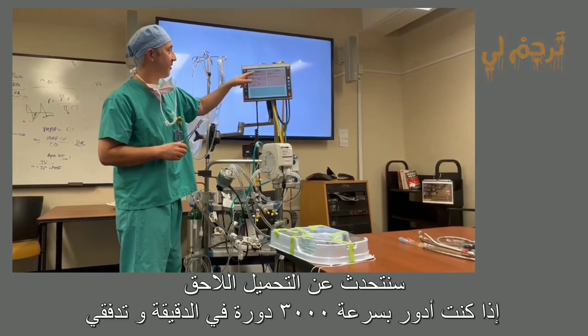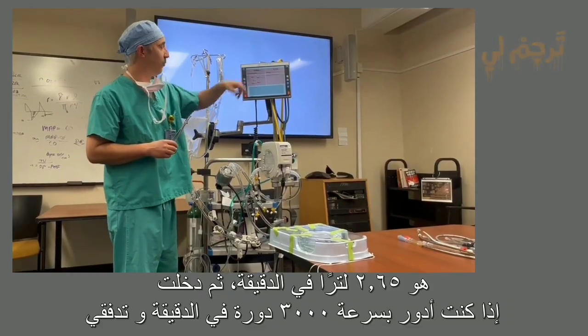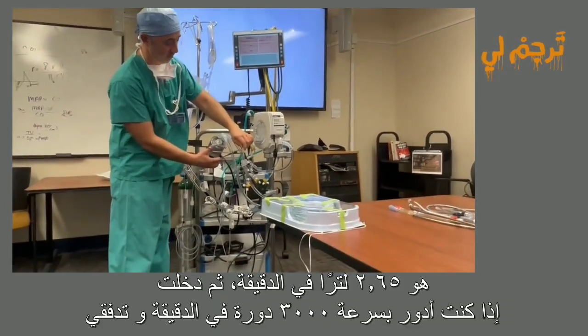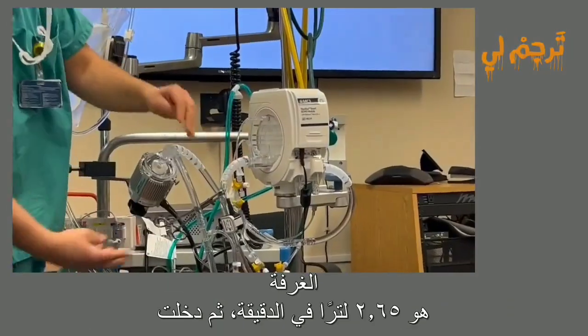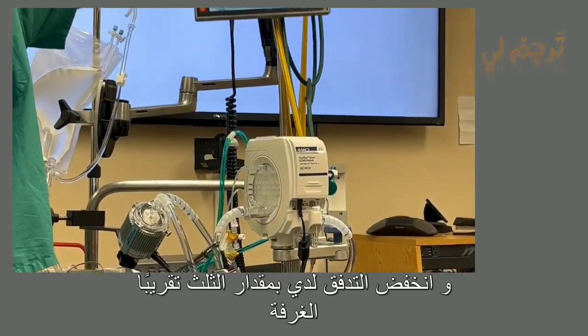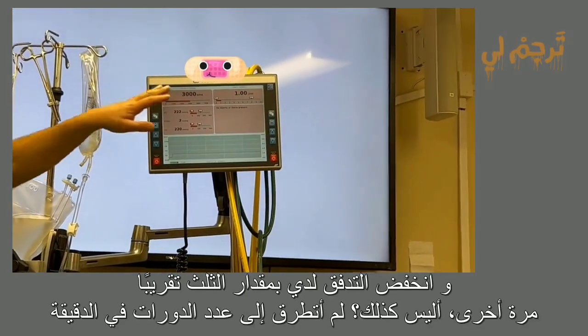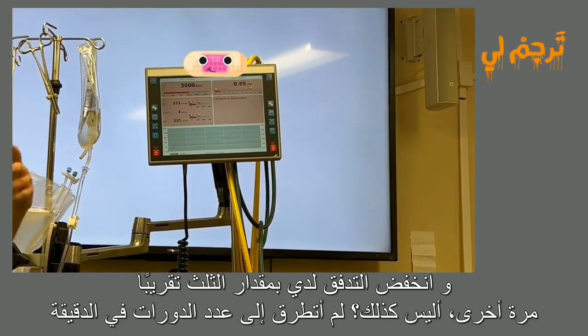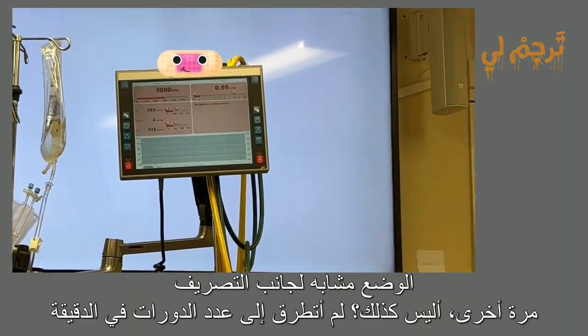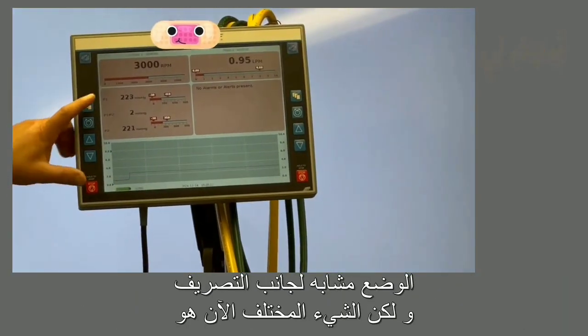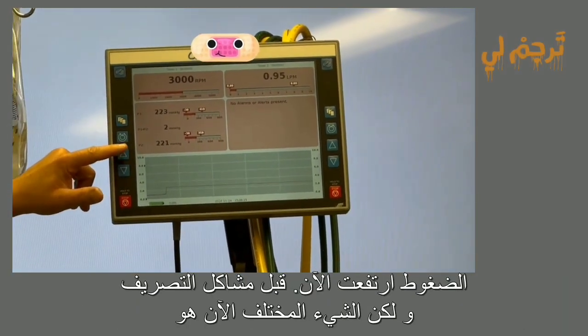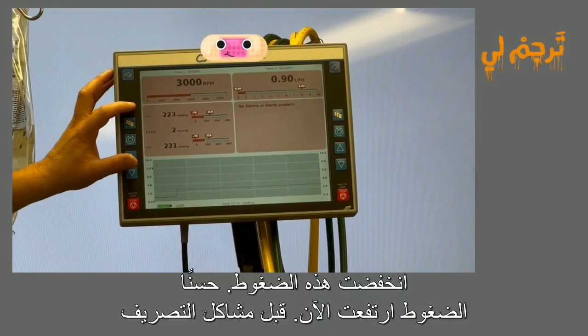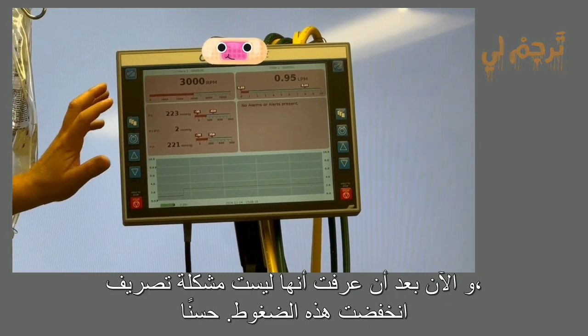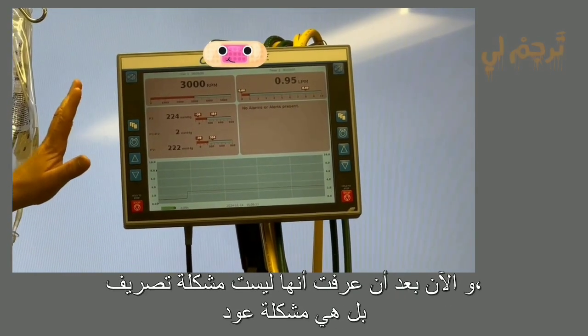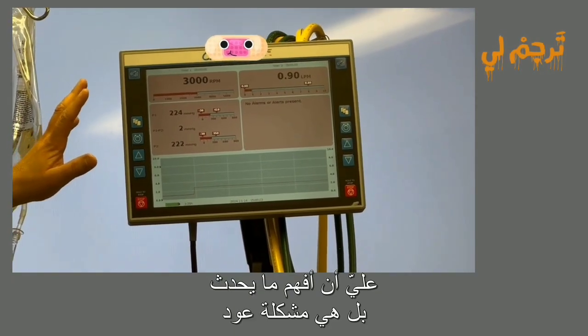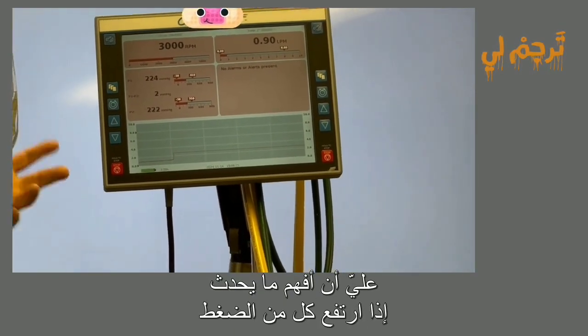If I'm spinning at 3,000 RPM and my flow is 2.65 liters a minute, and then I come into the room, now my flow is down almost a third, right? And I haven't touched the RPMs. Similar situation as the drainage side. The thing that's different is now my pressures went up. Before, with the drainage issues, these pressures went down. So now that I know it's not a drainage issue and it's more of a return issue, I've got to figure out what's going on.